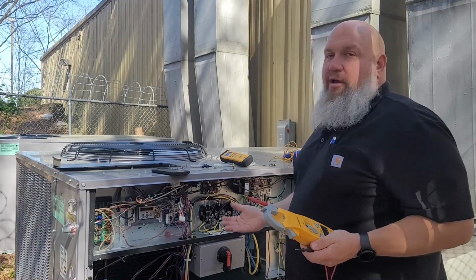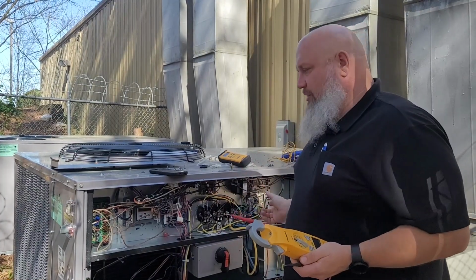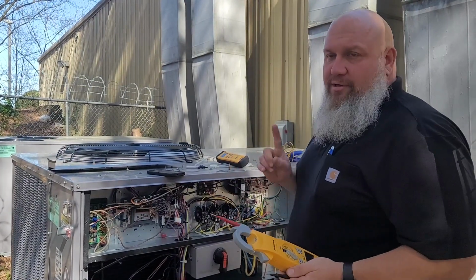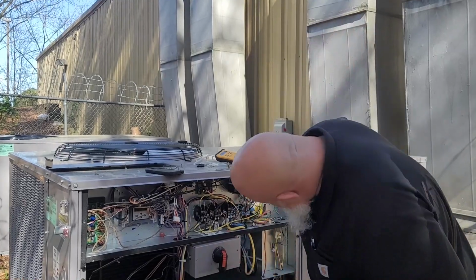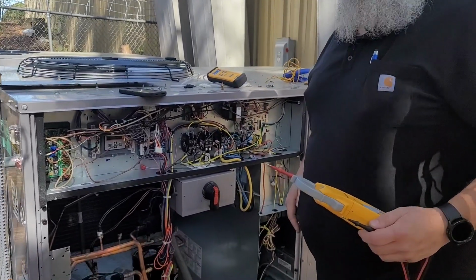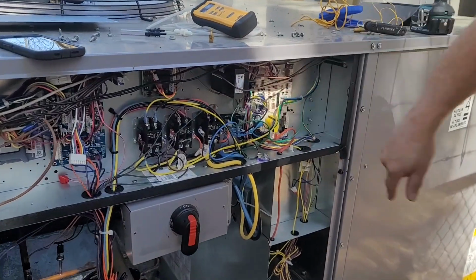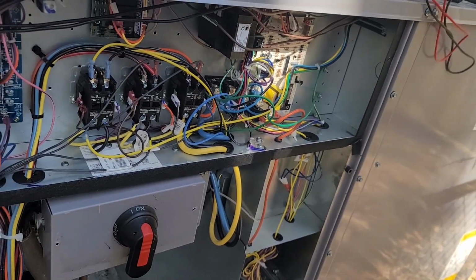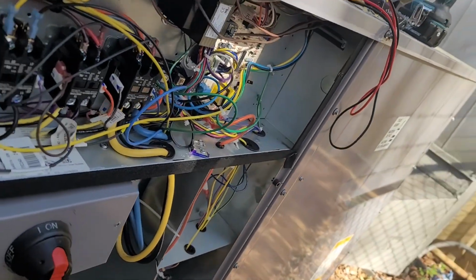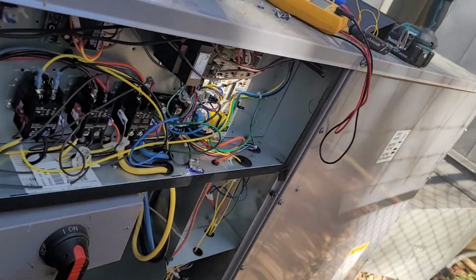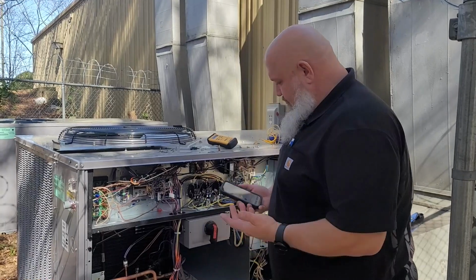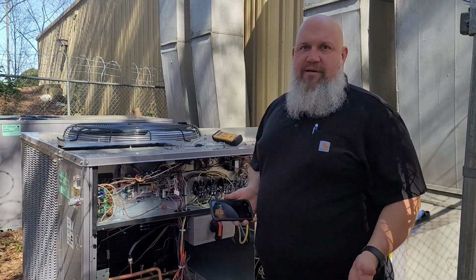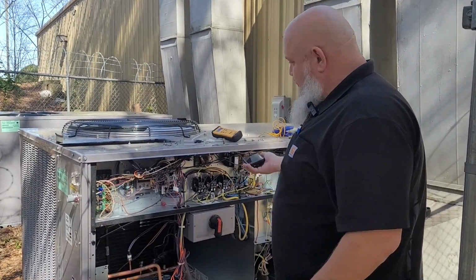If you don't have it set properly, you can cause all kinds of issues with these newer units. So you always want to make sure. This one is not set properly. This is set for 240 volt. You can look right in here and take a look. So what you want to do is go ahead and shut the unit power off and switch that over to the 208 volt side.